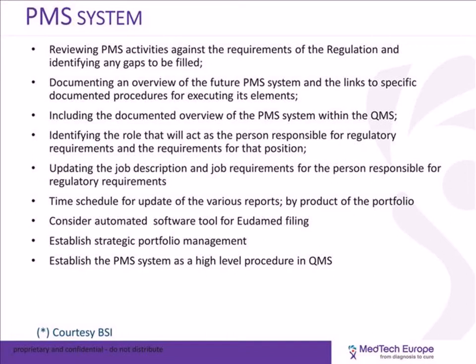Specifically, we need to make sure that the link with the documented procedure for executing its elements under the quality management system is very well defined. And the PMS system should become a very prominent part of the quality management system that needs to be reviewed at each management review.